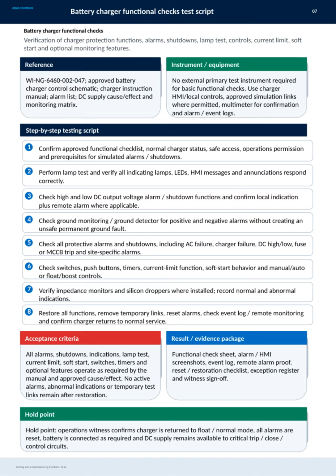Finally, all temporary links are removed, alarms are reset, and event logs are checked to confirm the charger returns to normal service. The acceptance criteria require that all functions operate as specified, with no active alarms or test links remaining. The result package includes the functional check sheet, alarm and event log screenshots, remote alarm proofs, reset checklists, and a witness sign-off. The process reaches a hold point only after operations confirm the charger has returned to normal mode. All alarms are cleared, the battery is connected properly, and DC supply to critical circuits remains available. This careful process ensures the charger operates reliably and safely within the electrical grid.